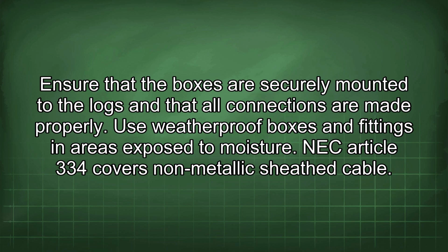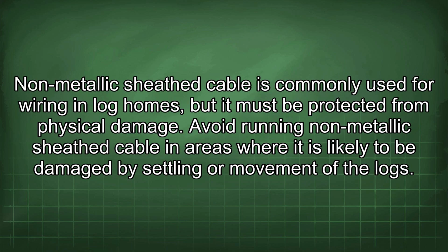NEC Article 334 covers non-metallic sheath cable. Non-metallic sheath cable is commonly used for wiring in log homes, but it must be protected from physical damage. Avoid running non-metallic sheath cable in areas where it is likely to be damaged by settling or movement of the logs.